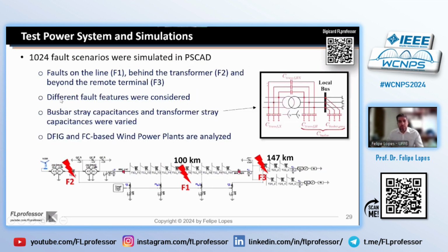So to demonstrate the effects of the stray capacitances on these functions, we simulated 1024 fault scenarios in PSCAD. And I would like to thank Moisés Davi for the support in doing these simulations. This is published and you can find it in our publications, but basically we simulated three faults.